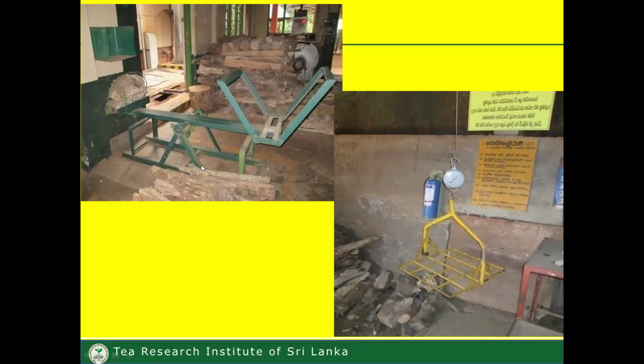They visit the factories in most cases once in 6 months, to check whether these boilers obtain their fitness certificates. Other than boilers, there are many pressure equipments, pressure vessels utilized in a tea factory. For color separators or color sorting machines, there are separate storage tanks to store compressed air. These also have to be checked by a properly licensed authorized person at least once in 6 months, so you should include these into your maintenance schedules.